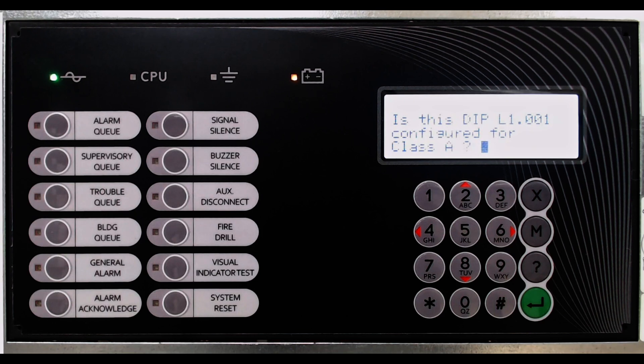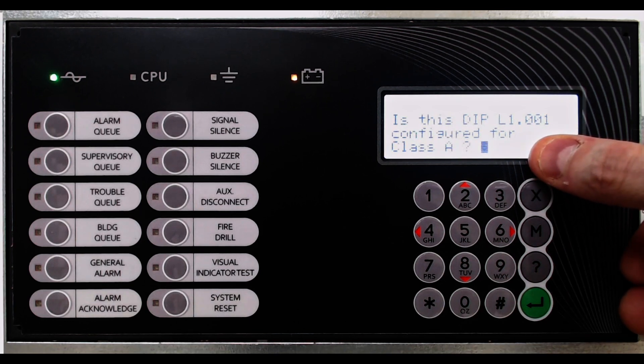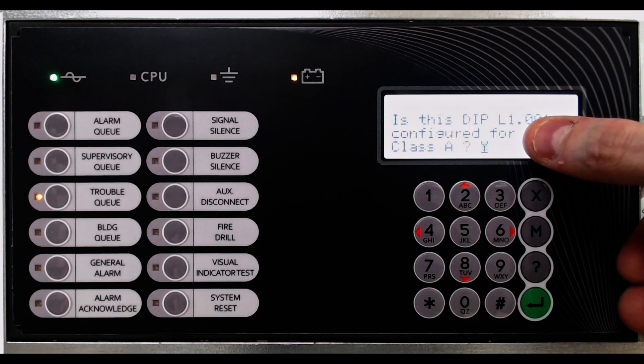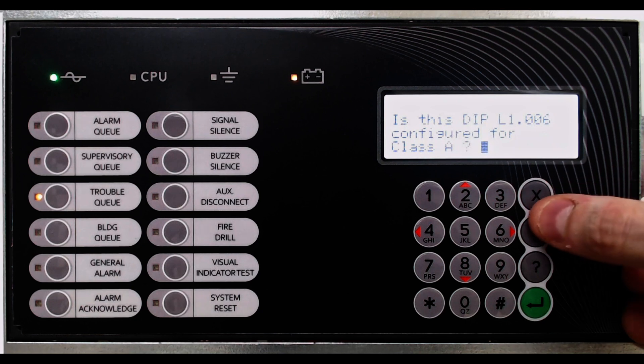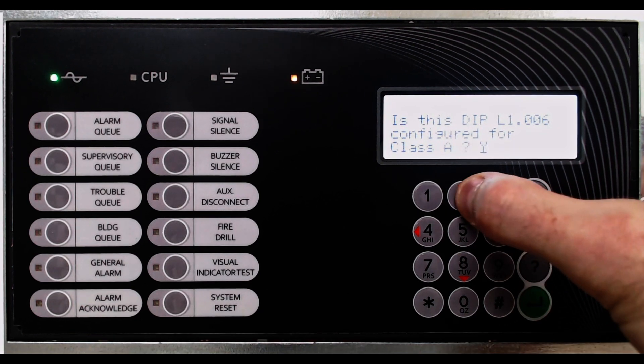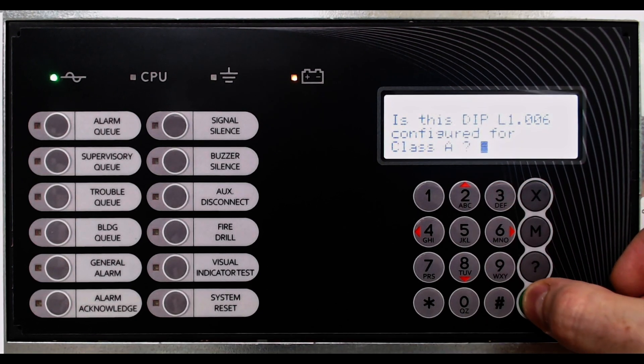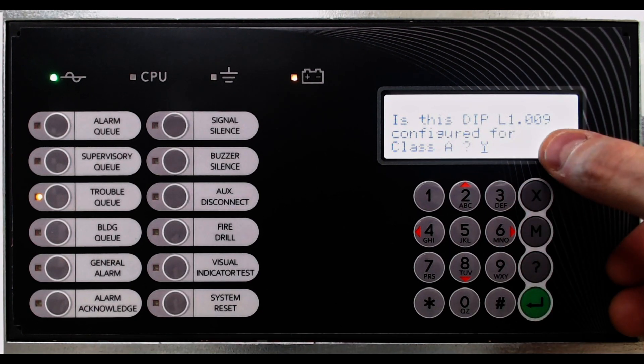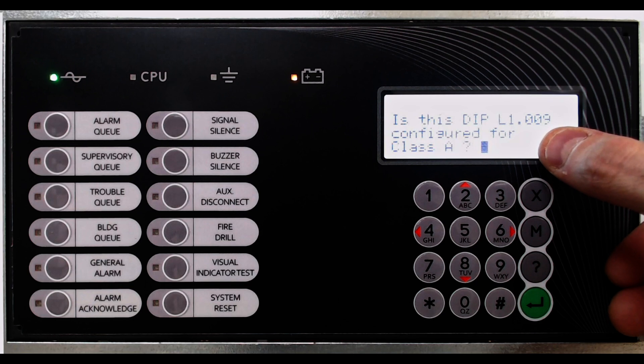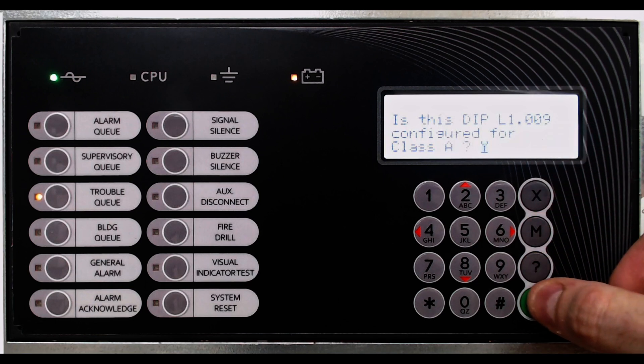The prompt asks, is this dual input module on Loop 1, Address 1, configured for Class A. The selection is Class A, Yes or No. Selecting No will set the device as Class B wired. Selecting Yes will set the device as Class A wired.